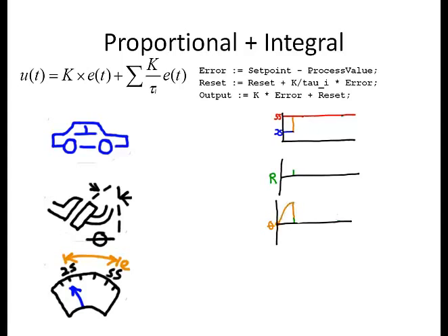This decreases the error, and this smaller error contributes a small increase to the reset register. The new reset register value is added to the output with the current proportional component, which results in the output decreasing and the car slowing down, which again increases the error. Over time, the proportional component oscillates as it did before, but the integral component continues to rise as long as the process variable is below the set point. The reset register will accumulate enough so that the car speed reaches the desired set point — and at that point, the proportional component has been reset to zero, which is likely the origin of the term.